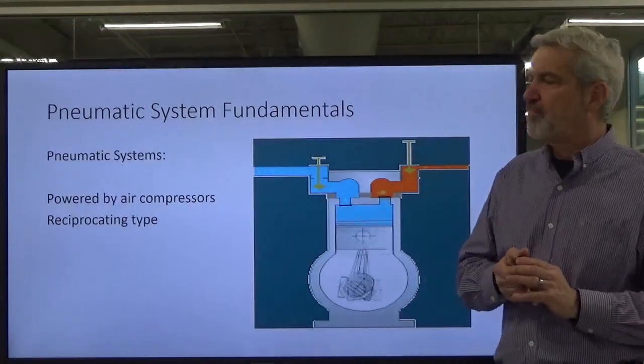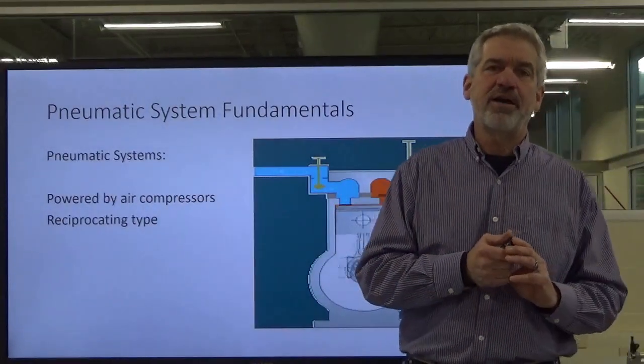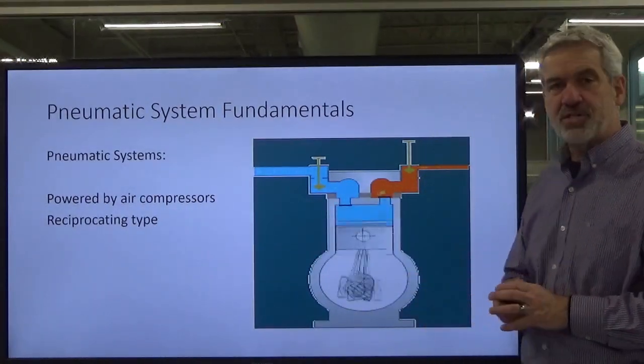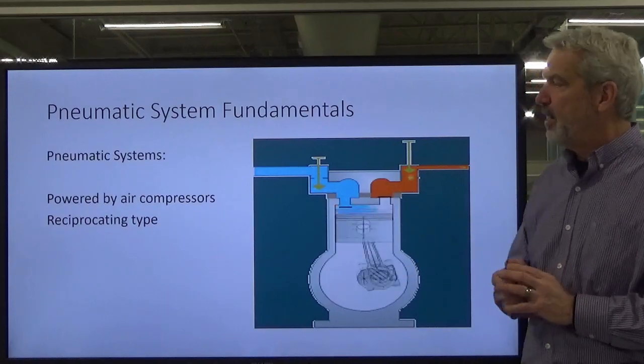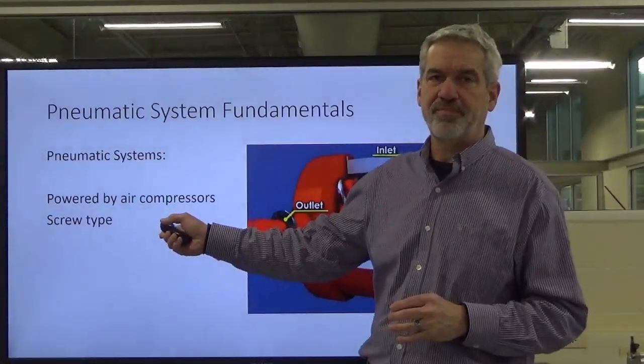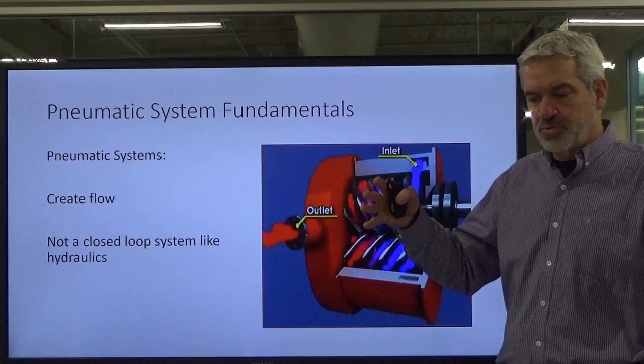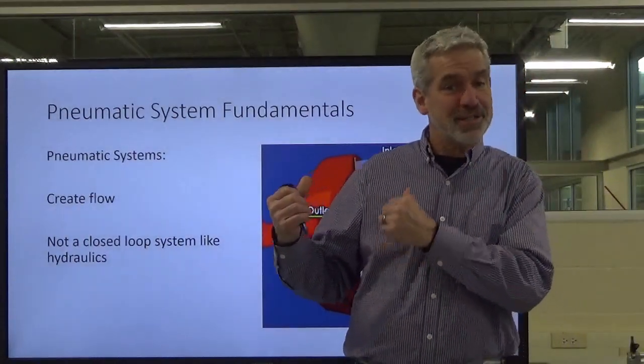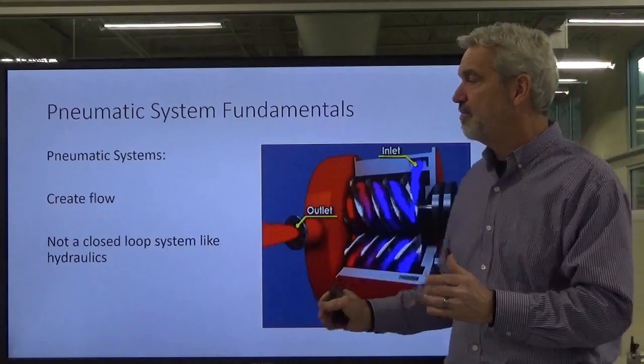We create flow with a couple of different types of air compressors. Number one is the reciprocating type. This probably reminds you of a gasoline engine with a single cylinder and a piston there. It's reciprocating, going back and forth. And there's another type, and it's known as the screw type. Now both of these take atmospheric air, and we will decrease its volume and increase its pressure. Mr. Boyle's law. See, I told you we were going to apply this stuff. So Mr. Boyle's law is already in effect. So we're creating flow.